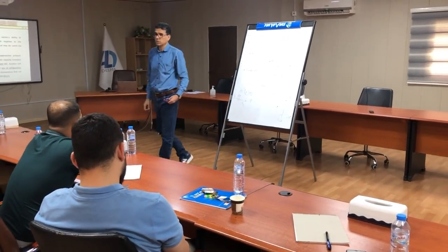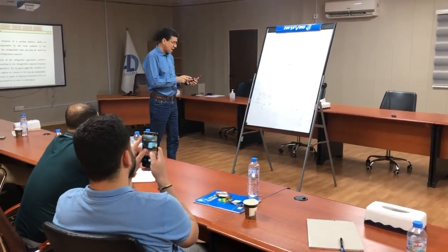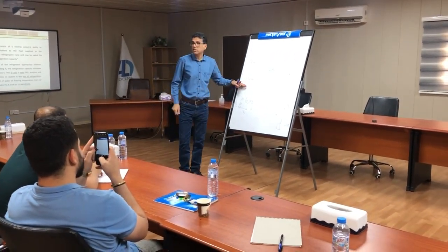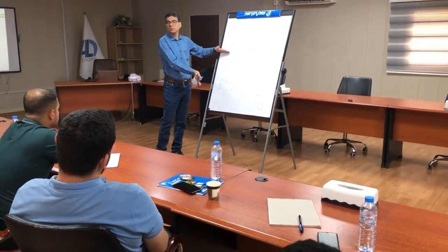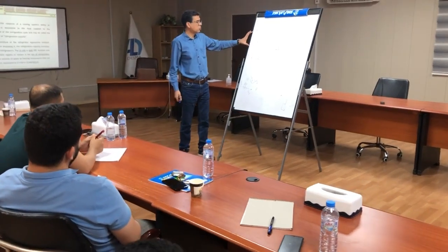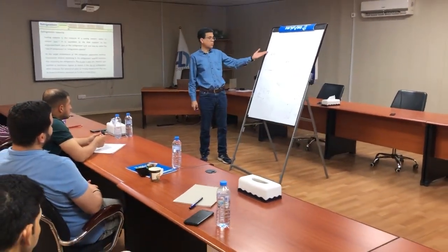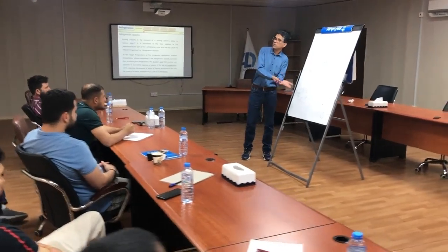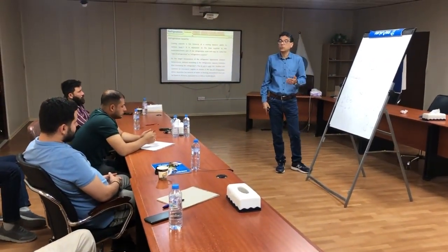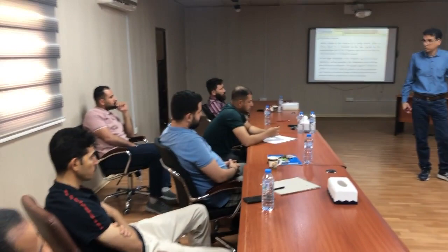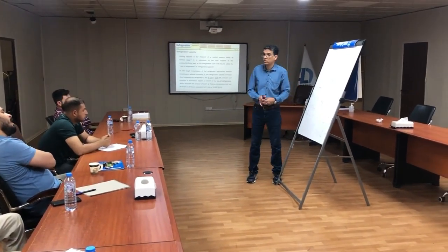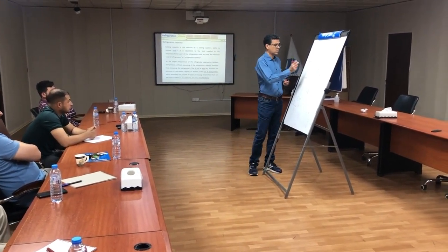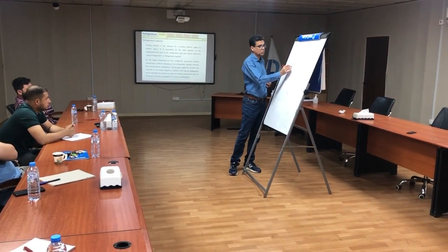This is the storage. For producing them, at first, if you can see, by the simple propane refrigerant we can remove this one. But we are not able to liquefy all of this one because we have propane over there. With the propane, we cannot condense another propane. Therefore, we have to use a turbo expander to reduce more temperature in NGL units. And as I explained to you, we have to use a turbo expander with cold box to reduce the temperature down to minus 82 degrees centigrade for this one.